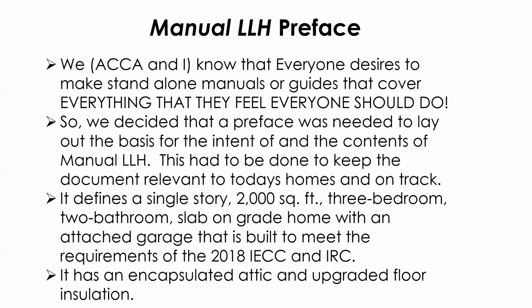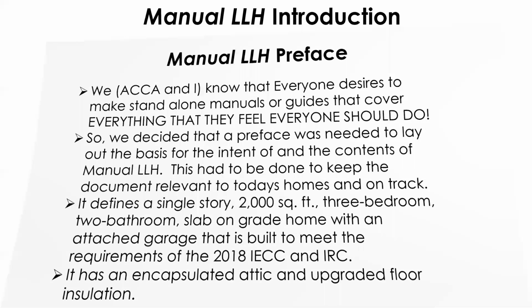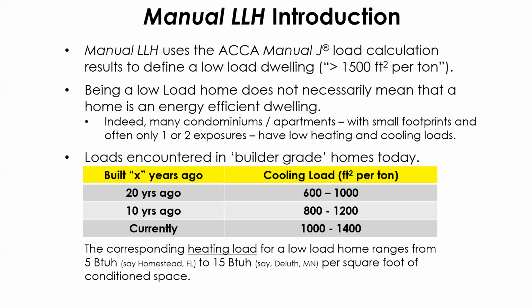It's exactly the kind of scenario we were hearing from Wrightsoft and other people that do Manual J's, saying, hey, we're doing a Manual J based on the current code, and we've got these issues. We need some help. The introduction defines what a low-load home is. Basically, you're talking 1,500 square foot per ton, the rule of thumb if you were going to go by that. And of course, a rule of thumb is always a good measure to go by, just to see, hey, am I in the realm of reality?